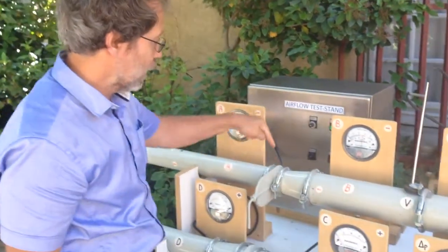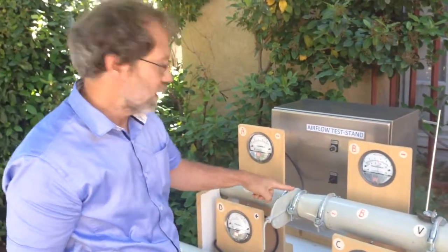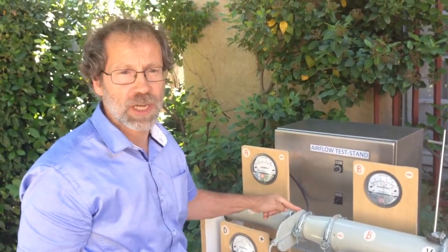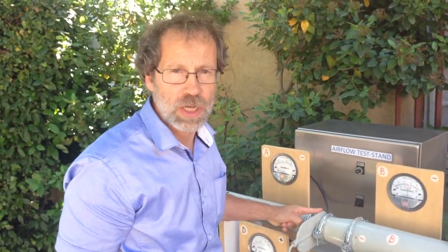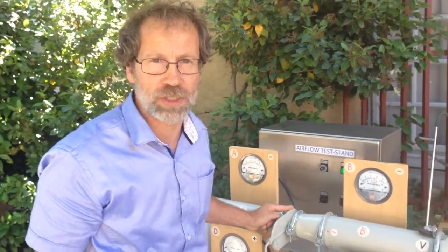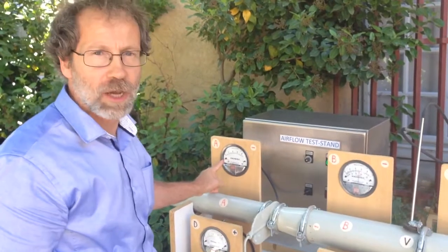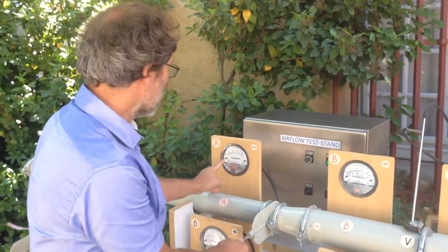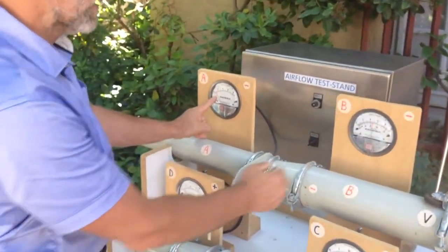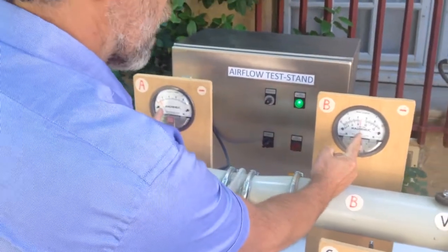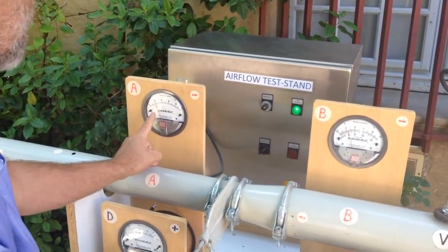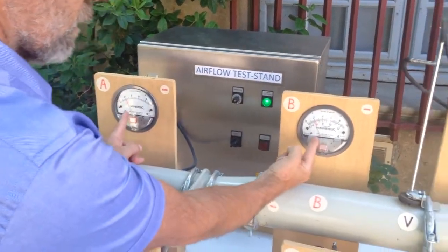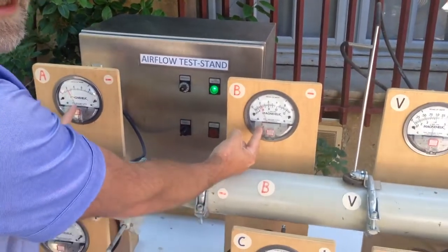That means, if we know this, with a simple gauge taking static pressure measurements across the system, we can say right here is a jump in the static pressure, and that means here is a resistance or blockage or partial blockage. In a total blockage, this goes down to 0, and in a partial blockage, it will create a certain delta P, which is very high now. If I take the resistance away, I will say, oh, now these two static pressures are basically the same.